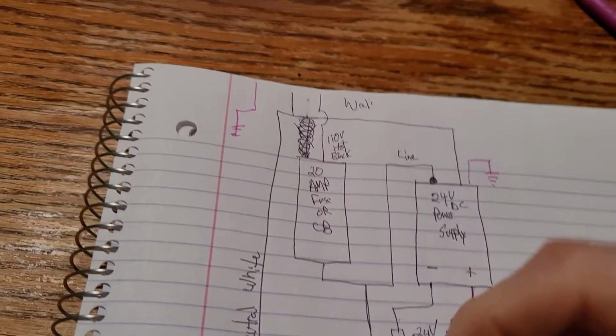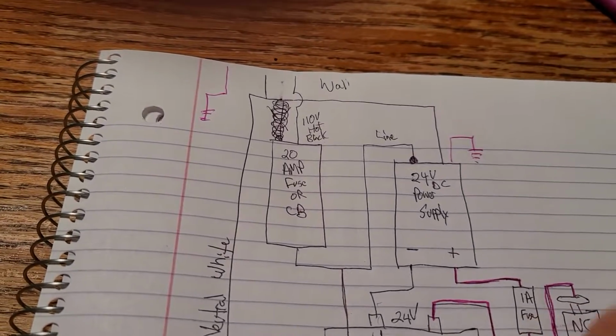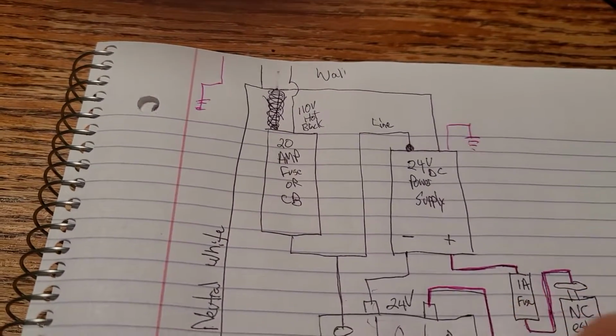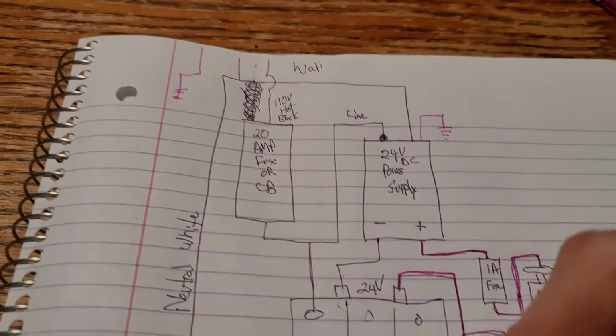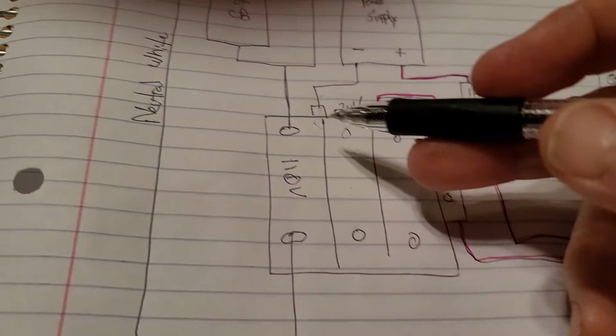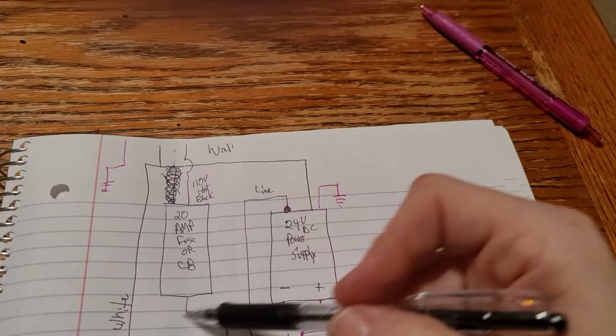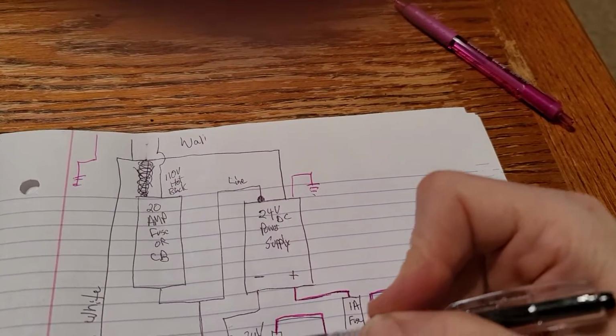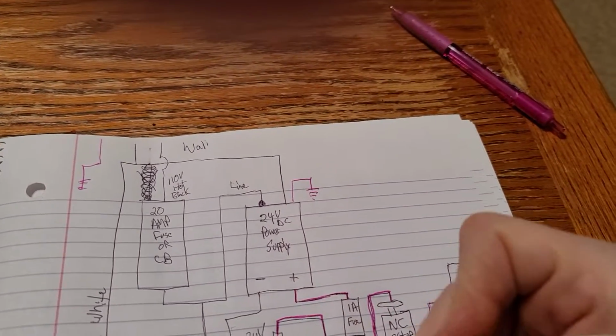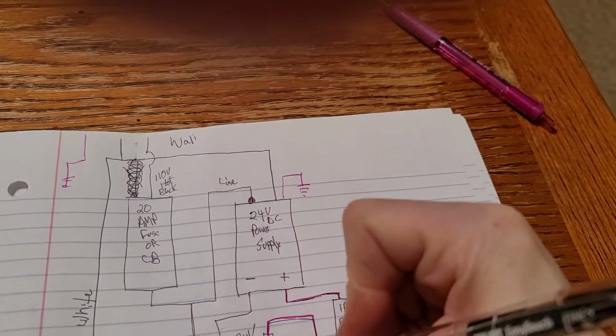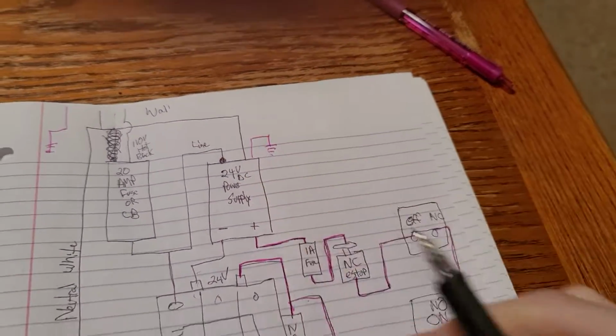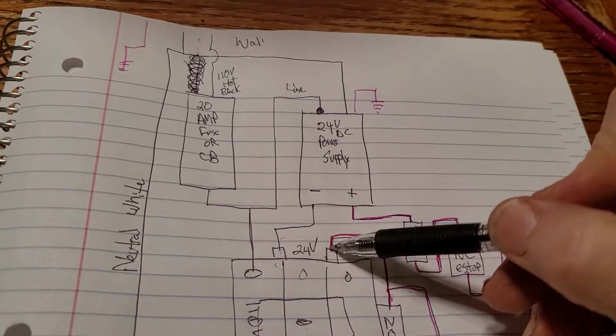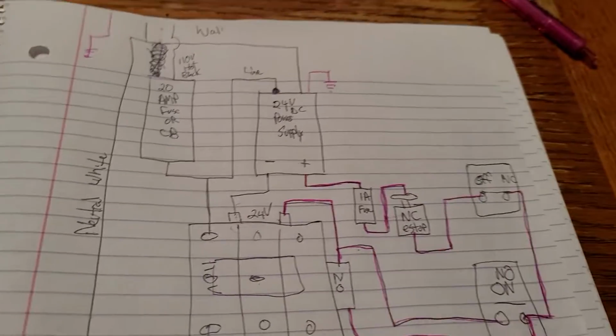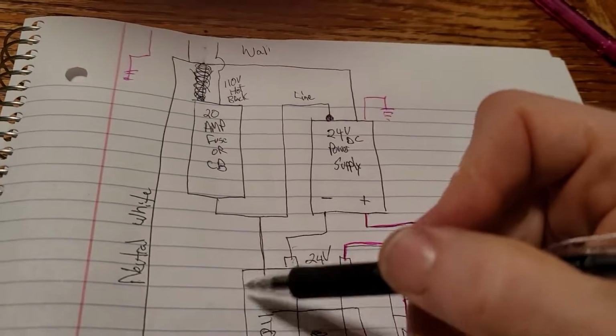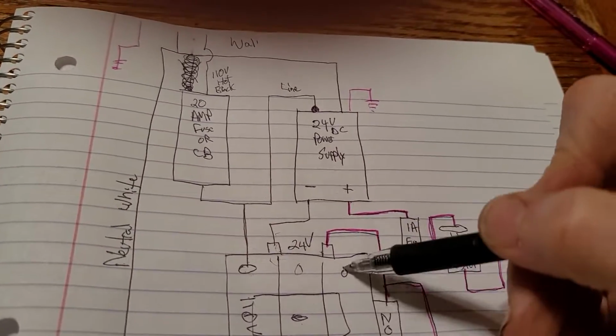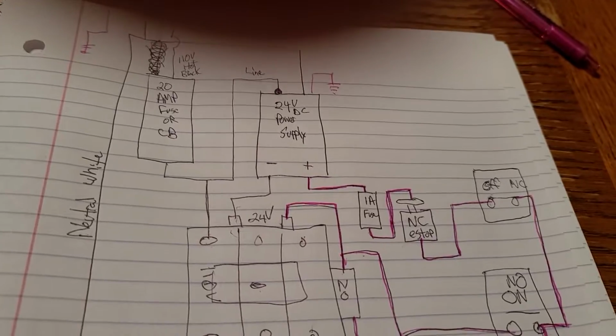And then you're also going to connect it to one of the main lugs, not the coil, but one of the three main lugs, what I call the high voltage side of your contactor. So what that does is it brings hot AC power into the top, but it's not connected until we supply voltage to the coil. When that happens, the center section sucks in. It makes a clunking sound. And then these three lines get connected, and that supplies the hot voltage out.